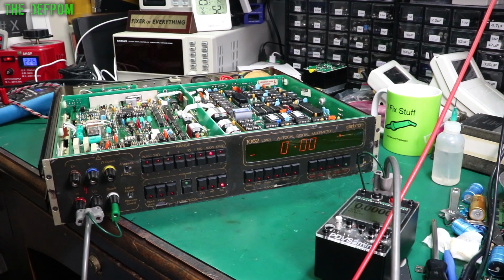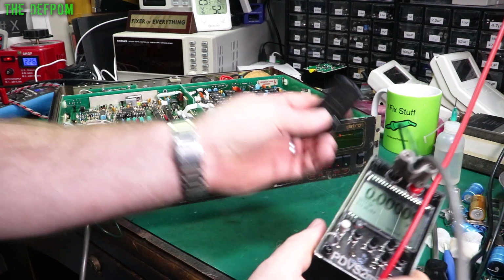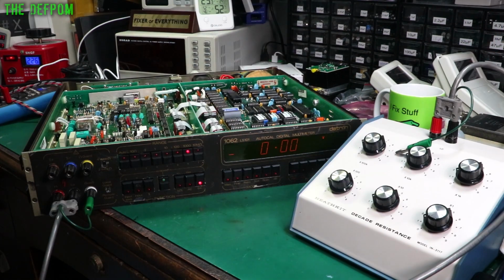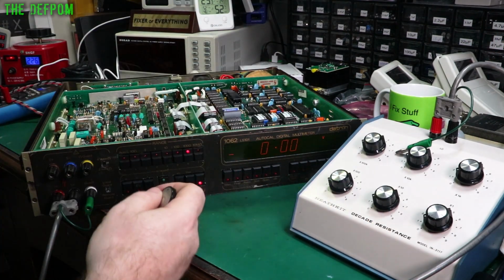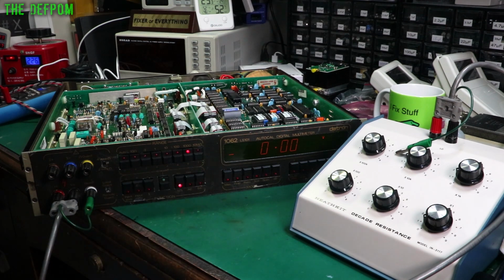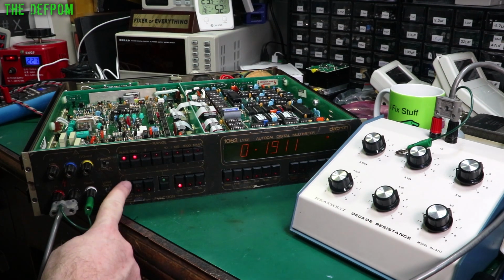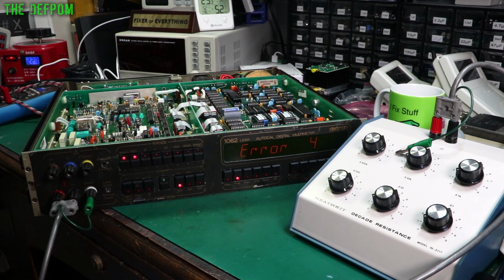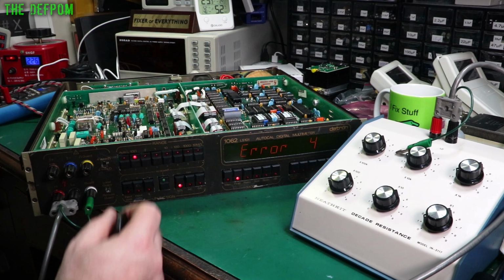Excellent. Let's just check resistance. If I can figure out where I put the remote. Oh, it's under here. Right, let's try resistance. We've got this box here set up. Let's go to the resistance ranges. And let's chuck on auto scaling. I've got it zeroed, so what I might do is just do an input 0, and go through each range and zero all of them. Oh, error 4. Calibration data is obviously so far out of whack it doesn't like it. So I guess you won't be doing that then.